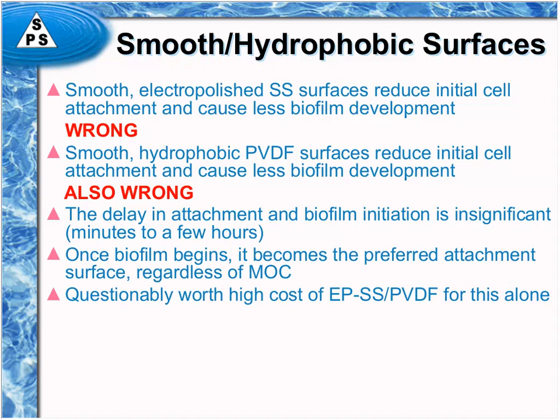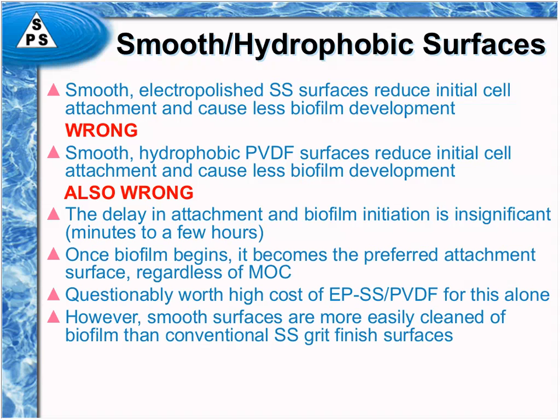It's the preferred attachment location. So it's questionably worth the high cost of electropolished stainless steel or PVDF if you're trying to reduce biofilm development. Now, the smooth surfaces are indeed easier to clean.